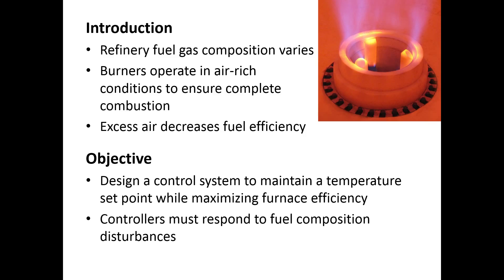This makes it difficult because in order to combust it properly you need to add the correct amount of air. Because the composition varies so much, typically they manually set the air valves to add a lot of excess oxygen, and what this does is decreases the efficiency quite a bit and makes it difficult to control the temperature of the burners.